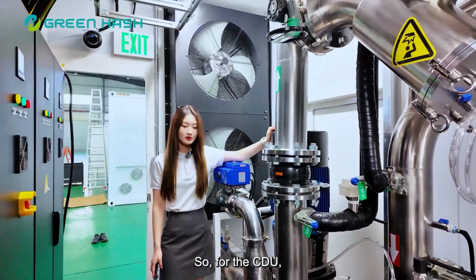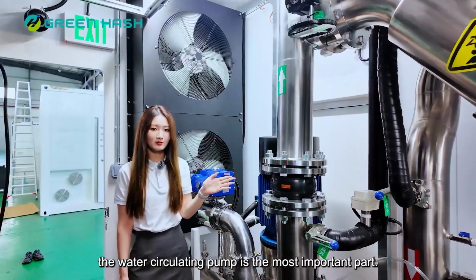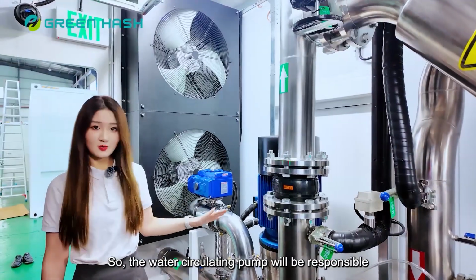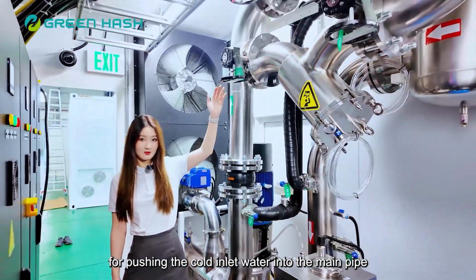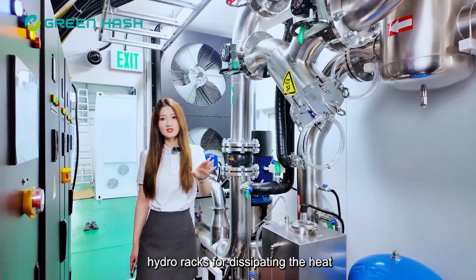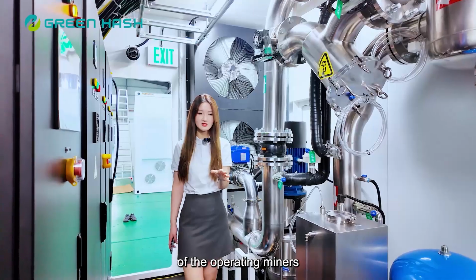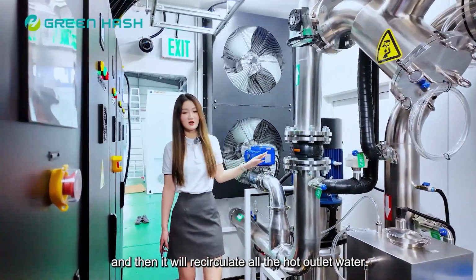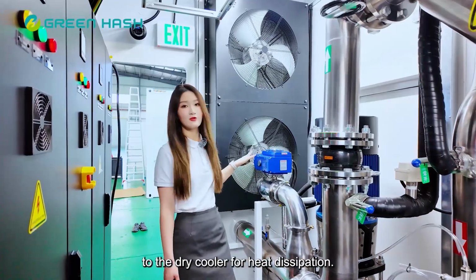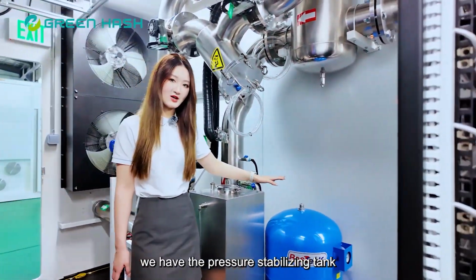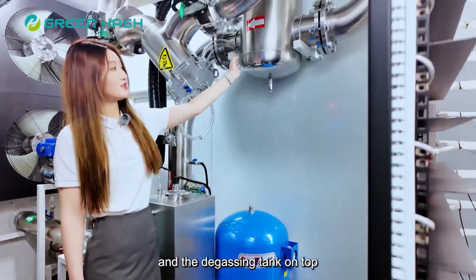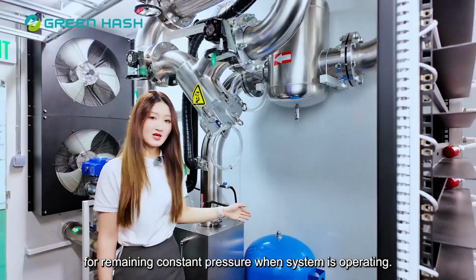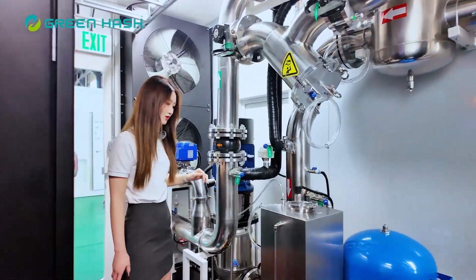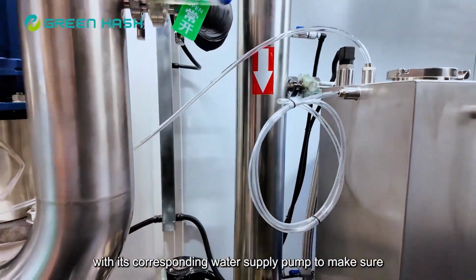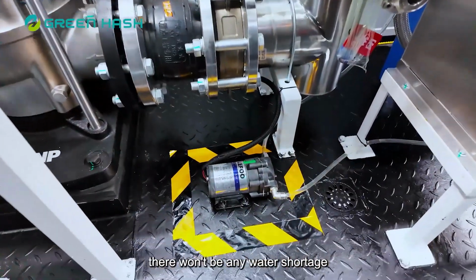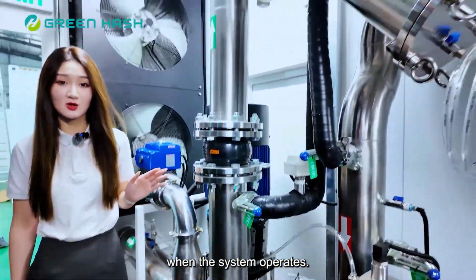For the CDU, the water circulating pump is the most important part. The water circulating pump is responsible for pushing the cold inlet water into the main pipe, and then distributing the water into the hydro racks for dissipating the heat of the operating miners. Then it recirculates all the hot outlet water to the dry coolers for heat dissipation. Right here, we have the pressure stabilizing tank and the degassing tank on top for maintaining constant pressure when the system is operating. And this is the water supply tank with its corresponding water supply pump to make sure there won't be any water shortage when the system operates.